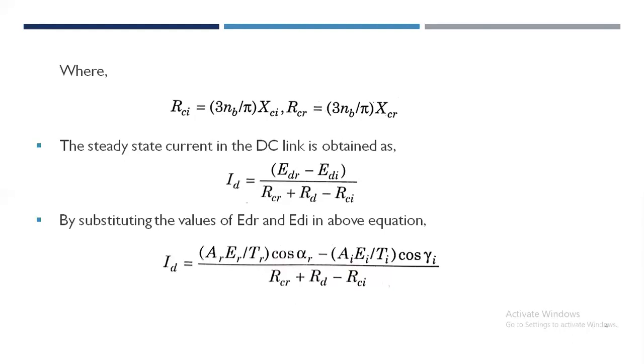The on-load tap changer control at the inverter is used mainly to maintain constant DC voltage. The tap changer control at the rectifier is designed to maintain the delay angle within certain limits, say 10 degrees to 20 degrees, in order to maintain a certain voltage margin for the purpose of current control. A voltage margin of 3% is generally considered to be adequate to meet any sudden demands for an increase in link current.